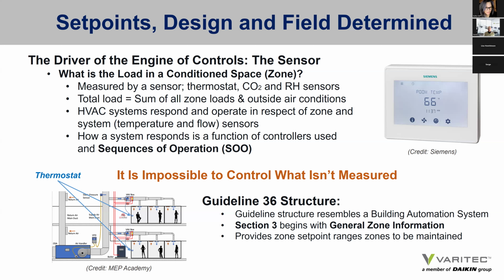HVAC systems respond and operate in respect of zone and sensor readings, and consequently send inputs into controllers for them to respond. So how a system responds is a function of controllers used and sequences of operation that directs how those controllers will operate under the given conditions as monitored and sensed.